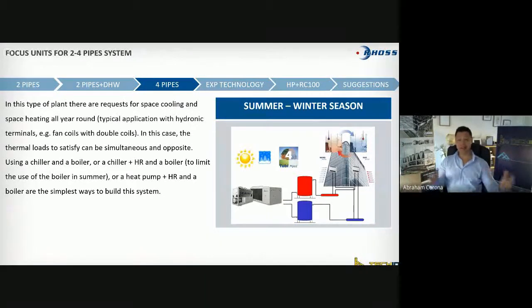And this is exactly when it gets messy, when you use a simple system. So in a simple system or a polyvalent unit, to get heat recovery, you need to run a demand of cooling, run the compressor, or a demand of heating, you need a reversible heat pump. There is a new class of heat pump. They are a little bit smarter. They can give you some advantages we want to explain at the end. But keep in mind that generally speaking, with any manufacturer, in order to have heat recovery, you need a demand of cooling or heating.